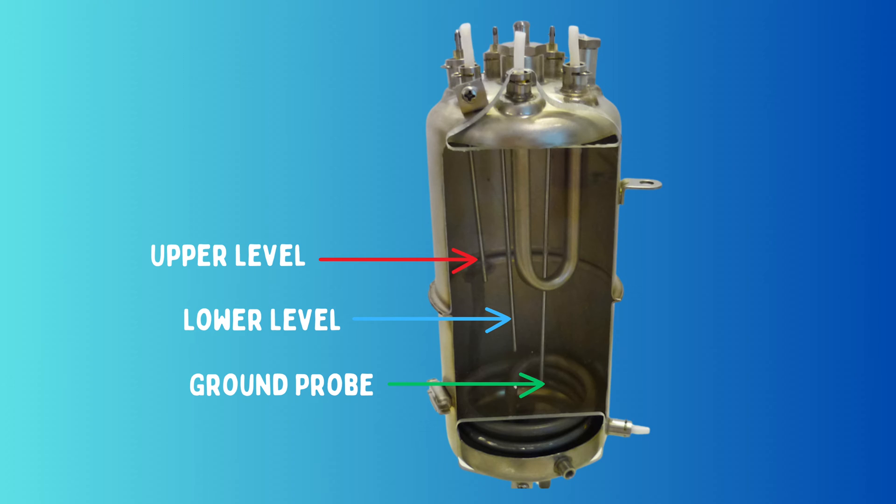The lower level probe with the blue wire is there to sense if the boiler can be switched on. You can see the tip is positioned just above the element to ensure it's fully submerged before it's allowed to get hot. The upper probe with the red wire tells when the boiler has enough water and can switch off the pump. This is about the halfway point.